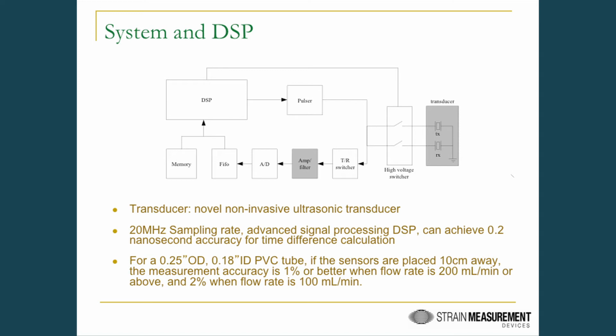We're now able to achieve better than 1% at 100 ml per minute, and we think within a couple of weeks, we just got some new boards in, we'll be able to achieve close to 1% at 50 ml per minute.